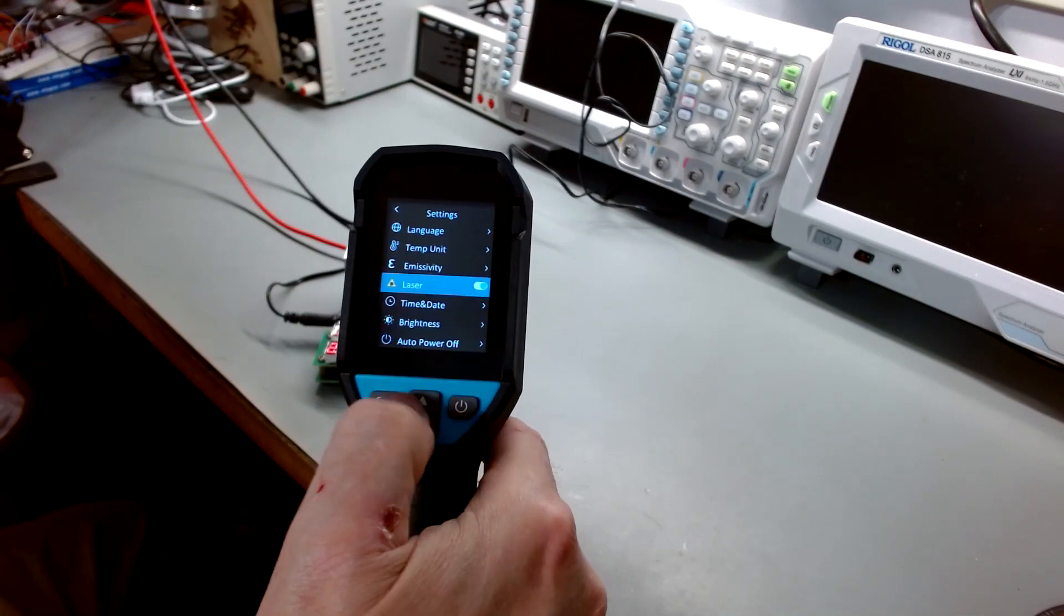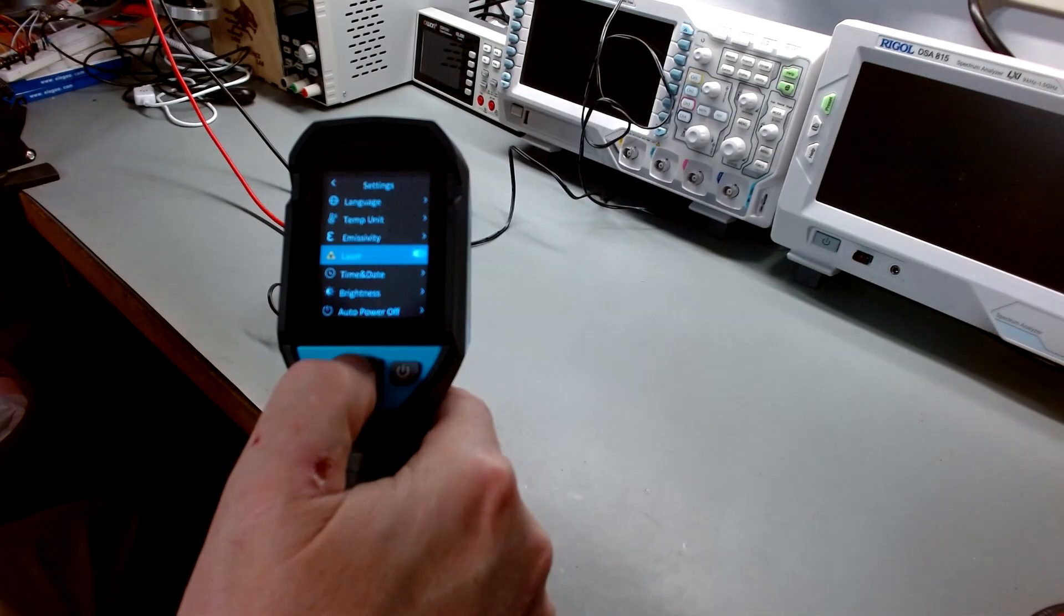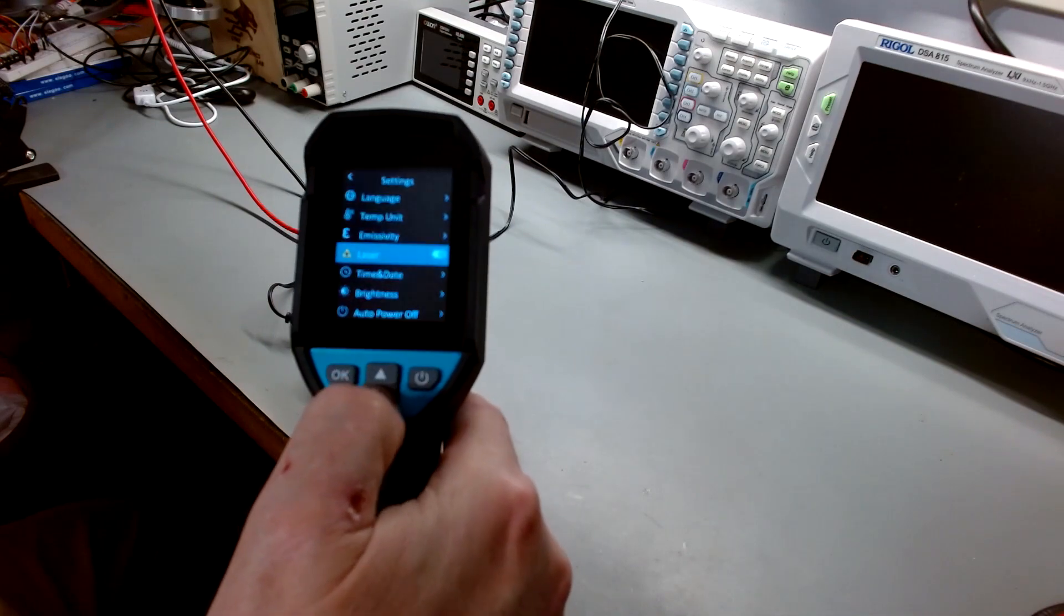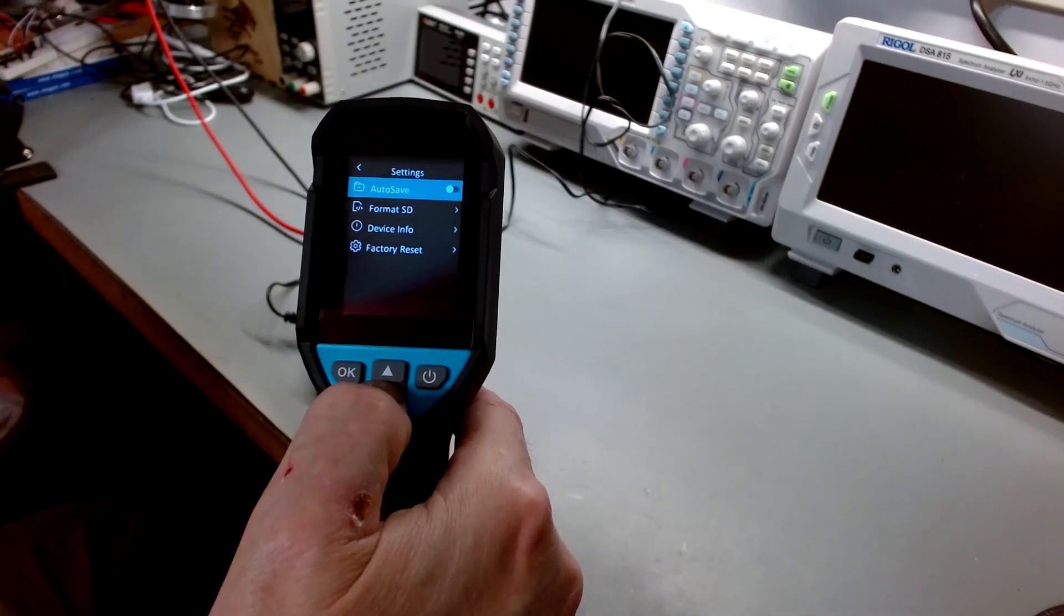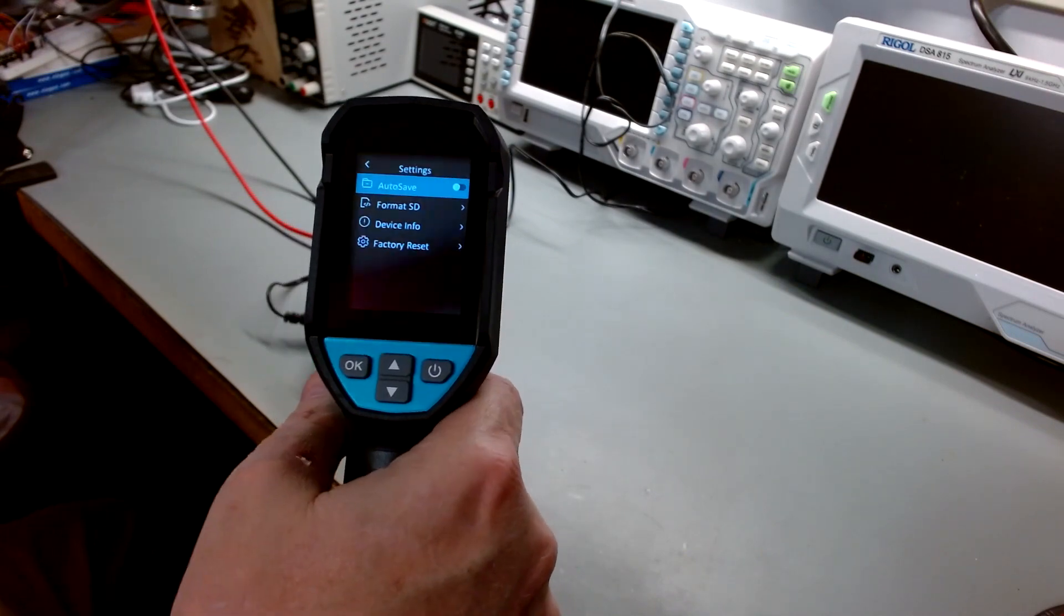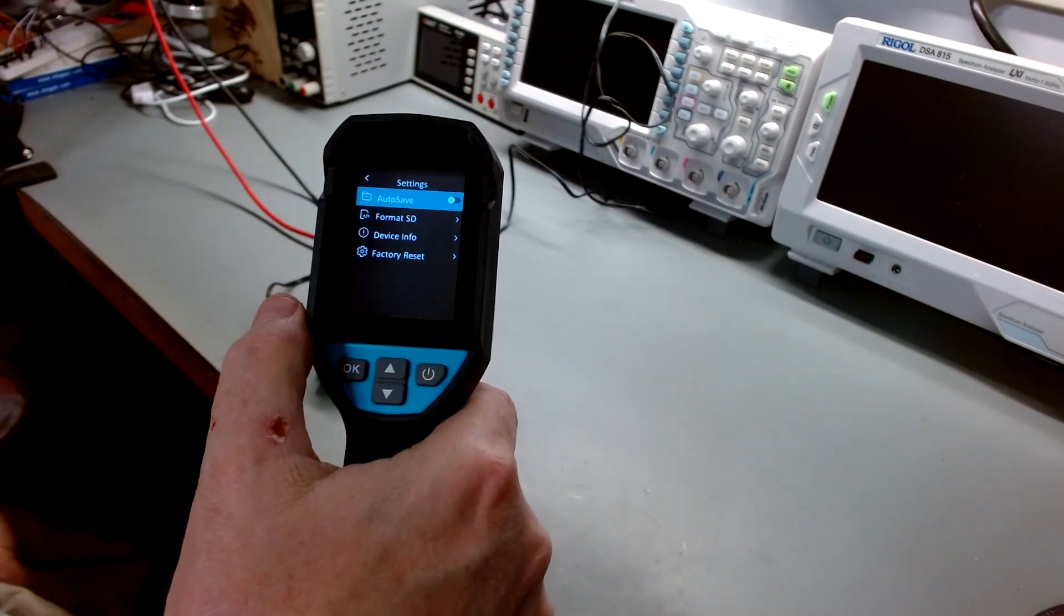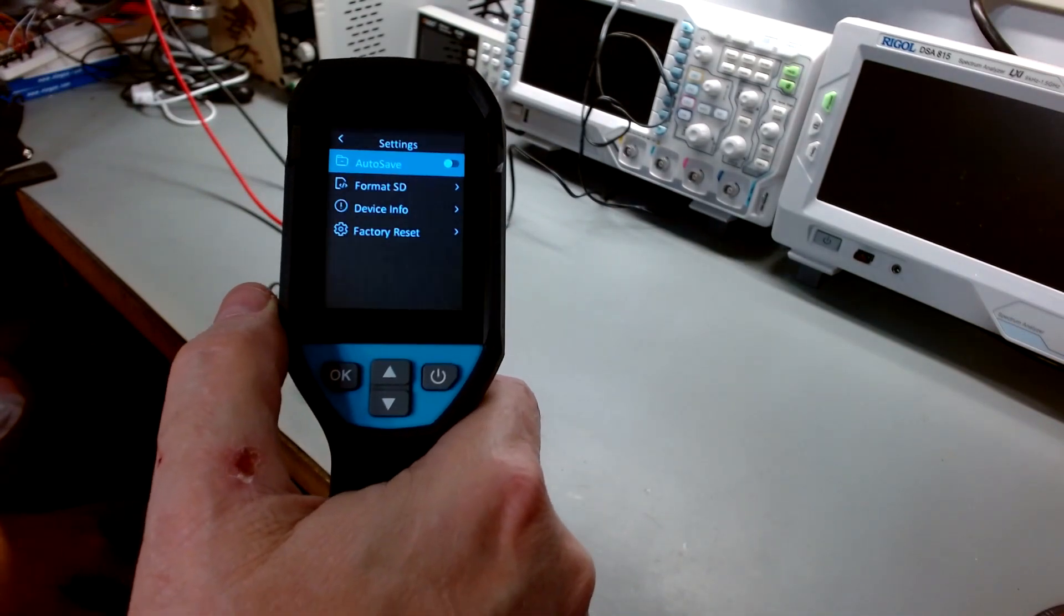Here's your main setting screen where you can change temp unit, emissivity, laser on or off, time and date, brightness, auto power down, auto save. That's where if you click the laser, it doesn't ask you. It won't ask you if you want to save an image. It'll just do it. You can format the SD card and then you can get device info and you can do a factory reset if you get it all boogered up.